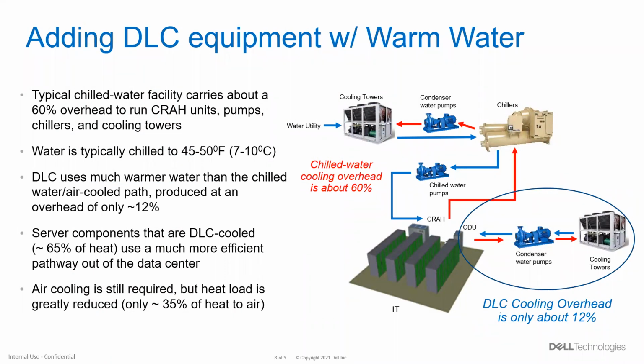One of the reasons that Dell is a fan of direct liquid cooling is it leverages warm water. And by warm water, what I mean is the temperature of the facility water that is going to be involved in the heat exchange between the IT and external to the data center can be as warm as 45 degrees C. What that means is you don't have to use chillers that require a lot of power to take the water temperature down to the 7 to 10 degrees C range. Chillers are typically used to create cool air in data centers. If you're able to eliminate a chiller out of the equation, your overall cooling overhead reduces by about 80%, which is a massive energy savings.